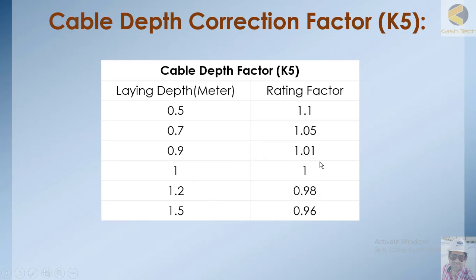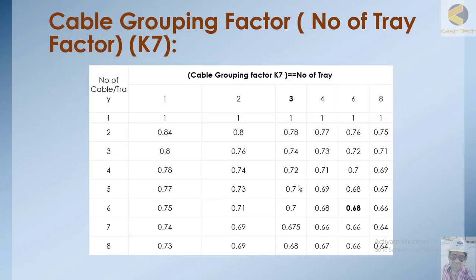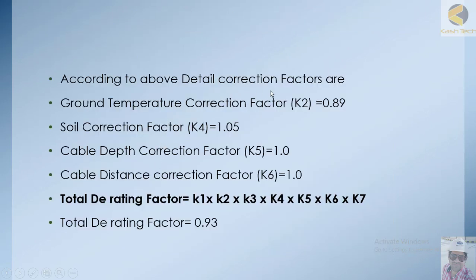Based on the cable depth we select the depth correction factor, and based on the distance between cables we select the cable spacing correction factor. Since we have no cable grouping — only one cable — we use a factor of 1. According to all the above data, the correction factors are: ground temperature correction factor K2 = 0.89, soil correction factor = 1.05, cable depth correction factor = 1, cable distance correction factor = 1, giving a total derating factor of 0.93.